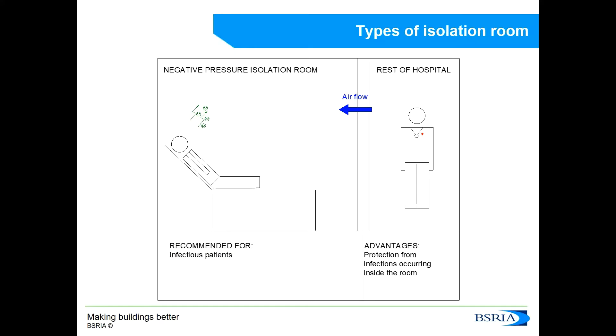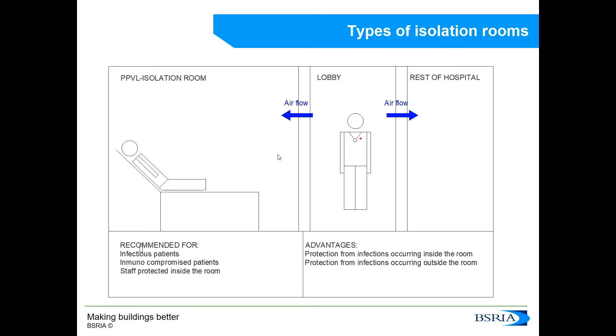On the other hand, when we have a patient that is infectious, we could put the patient into a negative isolation room to ensure that air travels from the rest of the hospital into the isolation room, successfully containing the infection. However, we also have to think of patient protection, as infectious air from outside may come into the isolation room. A solution is to build an airlock — a pressurized area at higher pressure than both the hospital and the patient's isolation room — so air cannot travel from the hospital into the isolation room or vice versa.